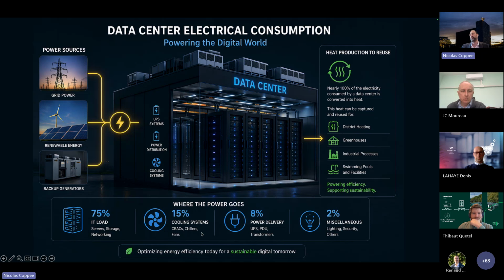Hopefully in Belgium, not everyone's happy with the temperature, but for us it's good for data centers, since the norm is between 17 and 27 degrees, and most of the time we're looking at 21 to 25 degrees in front of the servers. So 15% of consumption goes to cooling, 8% to electricity distribution due to UPS efficiency and generator preheating, and the last 2% to other utilities.